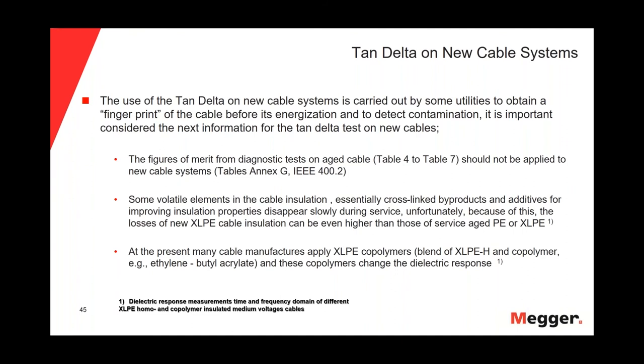To finish the presentation, I'd like to discuss the use of the tan delta on new cable systems. Some customers use the tan delta on new cable systems to get a fingerprint of their cables or to detect contaminants in the insulation. If we do tan delta on new cables, it is very important to keep in mind the following: the figures of merit — the tables in IEEE 400.2, specifically tables 4 through 7 — should not be applied to new cable systems. For new cable systems, we need to use the new cable tables in IEEE 400.2.